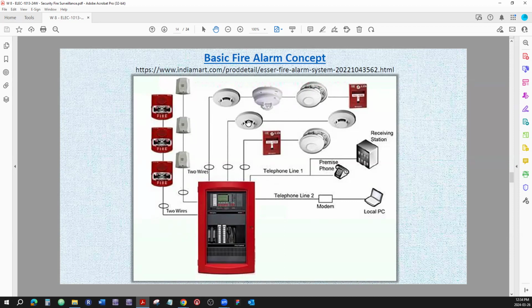So let's say this smoke detector is going to be triggered. All right, it's going to appear on the panel, and the panel is going to be put in test mode. And the resetter is going to communicate through a cell phone or maybe walkie-talkie to the person. Says, oh yeah, I see that this so-and-so labeled smoke detector was triggered. Okay, reset, next. So the resetter presses the reset button, and the technician goes and triggers something else. Right? And that sometimes can take a whole day, depending on how big the facility is. And those annual inspections are every year. Right? Also, fire technicians deal with fire extinguishers.